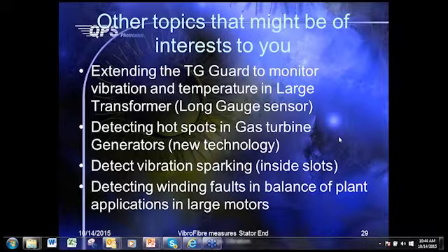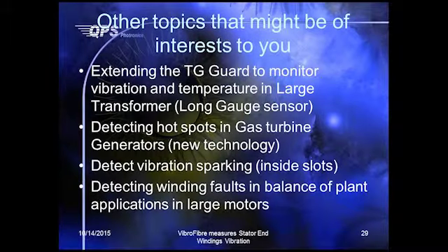But since gas turbines are smaller and operate at higher current density, people are starting to be concerned about hotspots. These hotspots are due to eddy current introduced via damages when they stick the laminated steel plates together, forming the core.